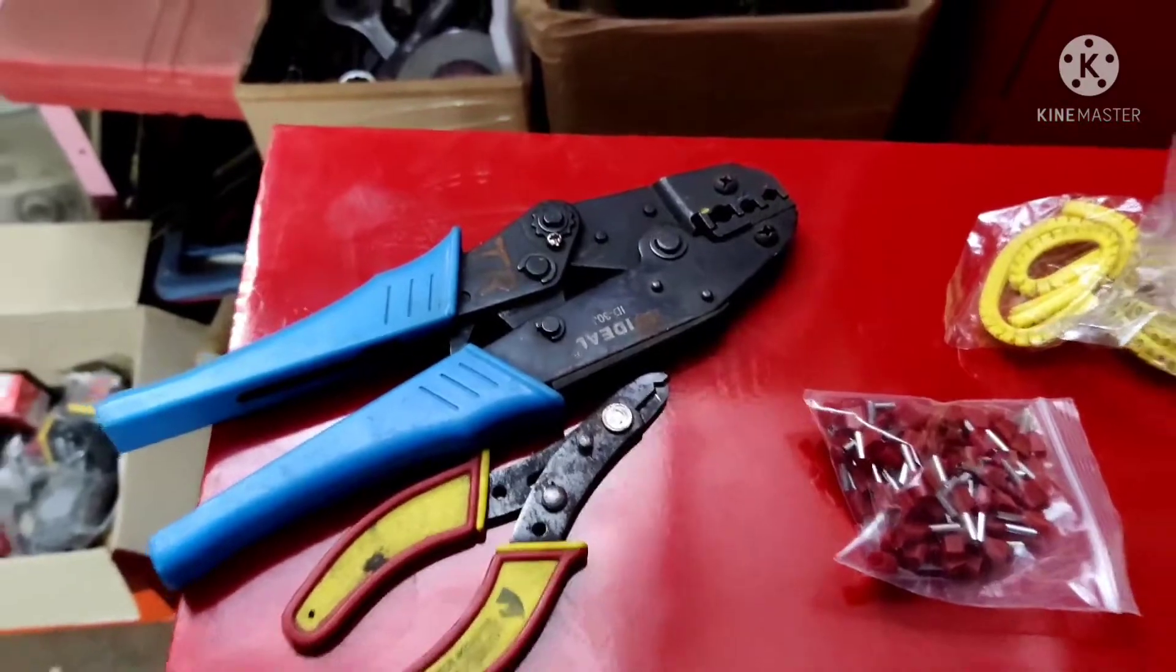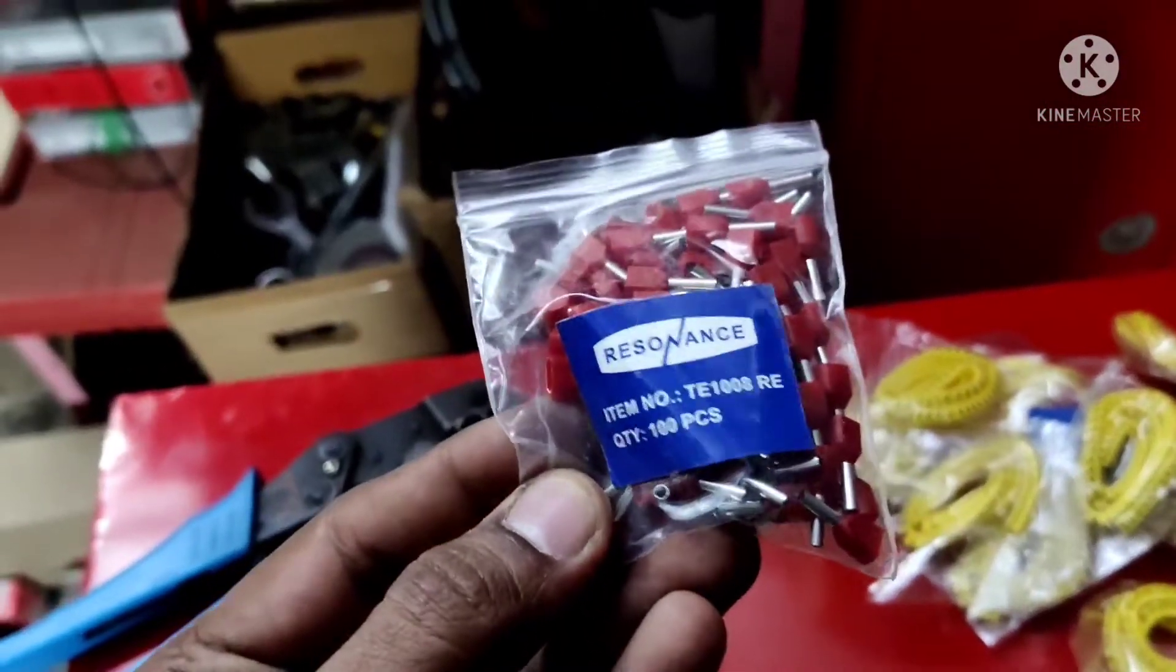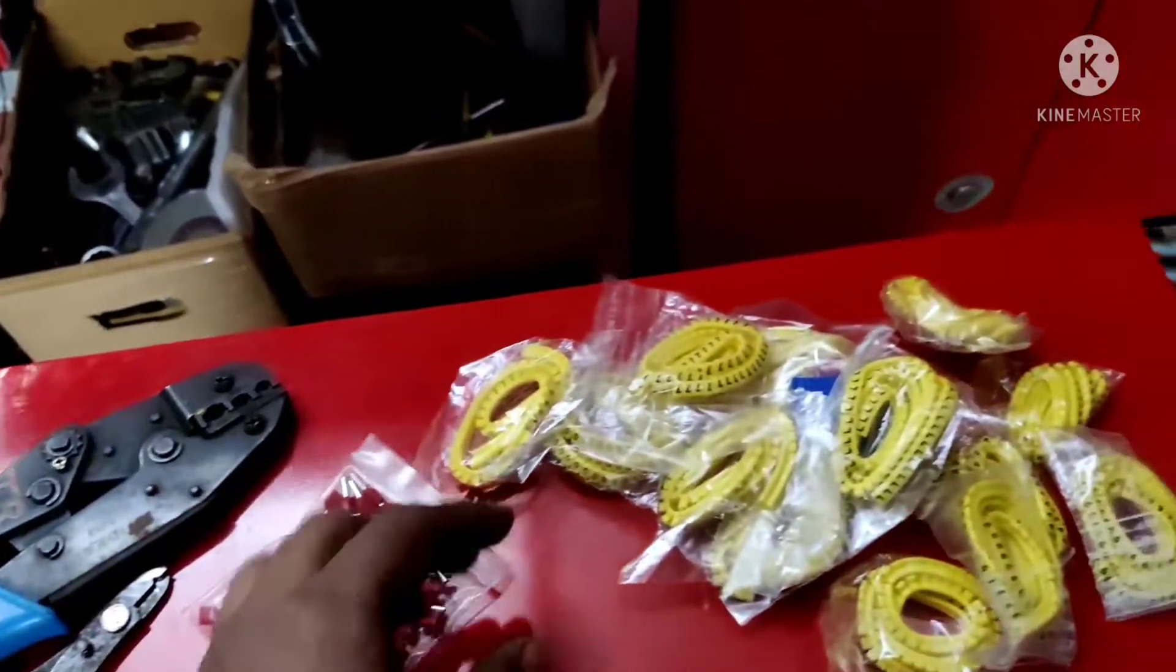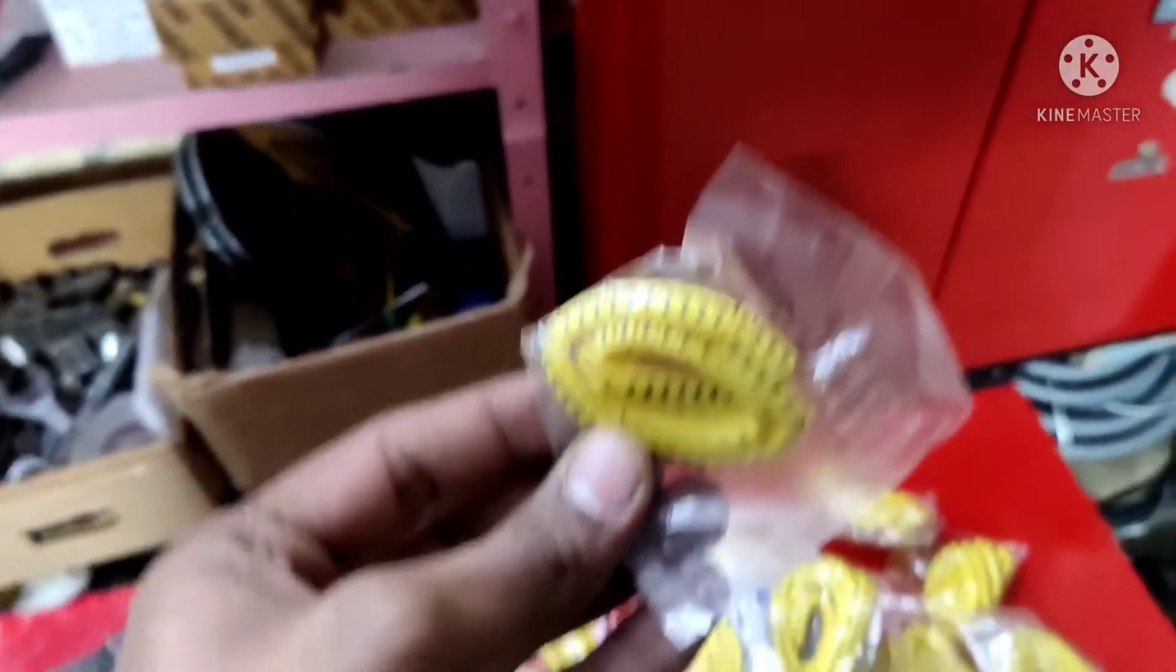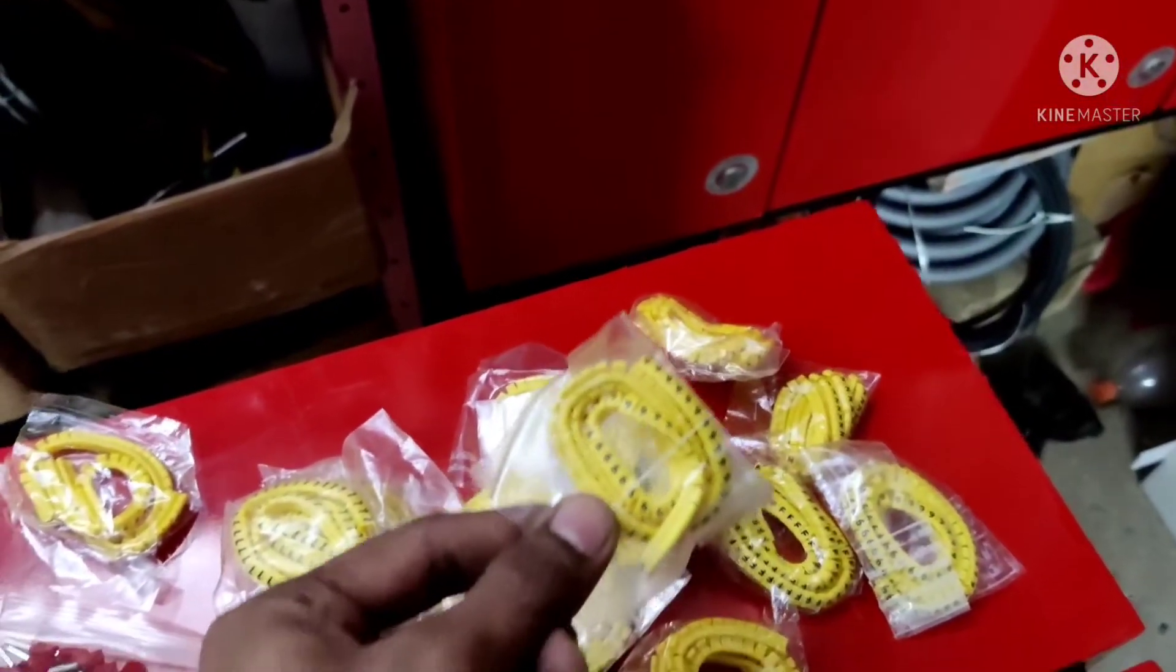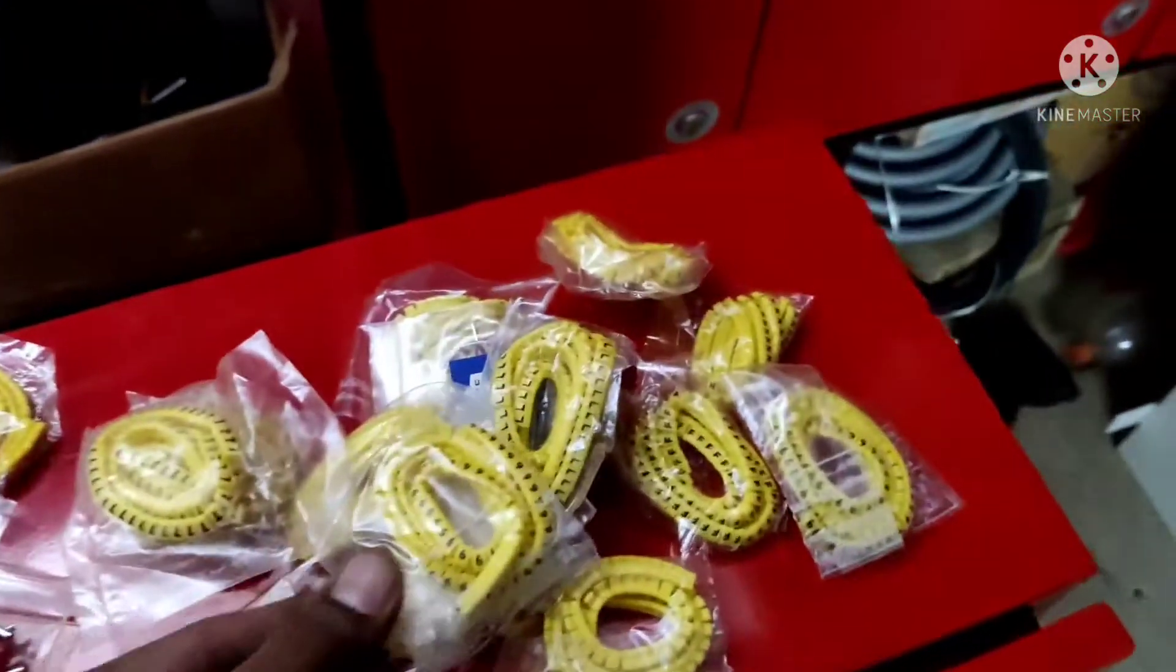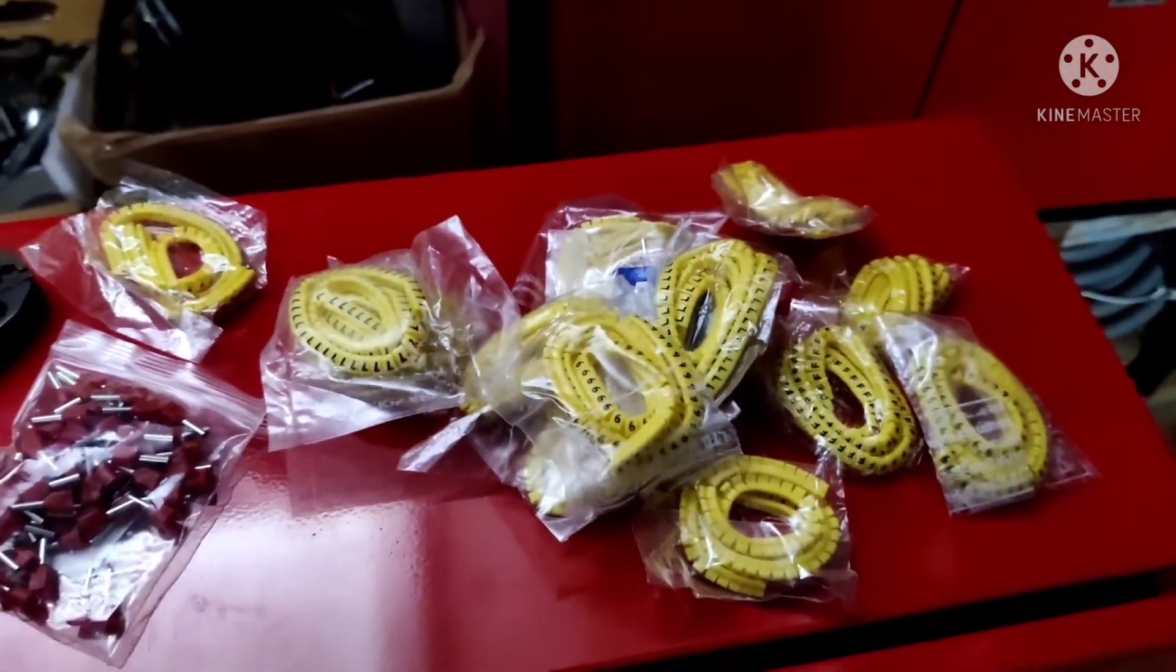The blue colored tool is called a crimper which will be used for crimping these lugs. These are numbering ferules used for addressing the wire terminations. Each and every wire termination has its own unique ferule number which is prescribed in control wiring diagram.